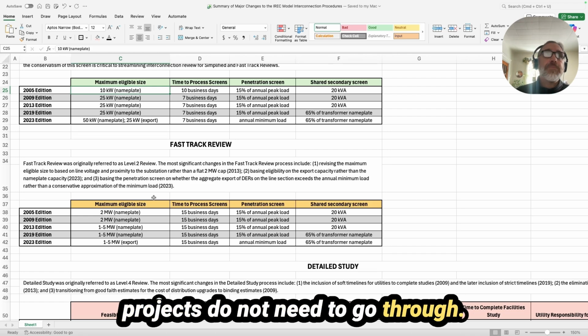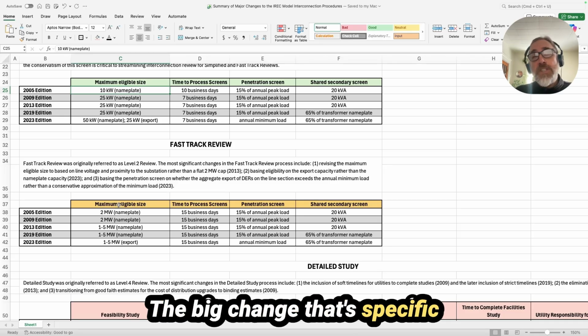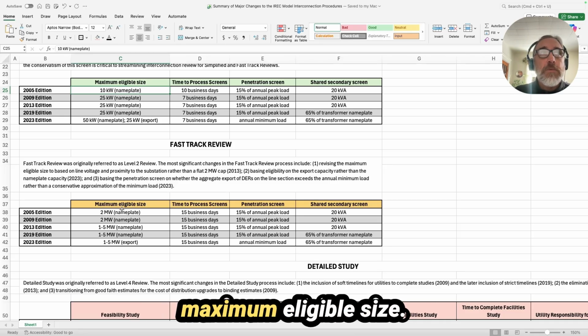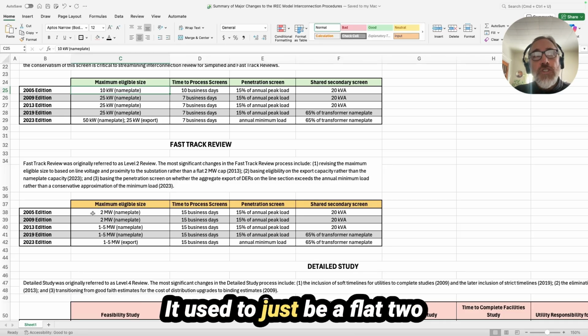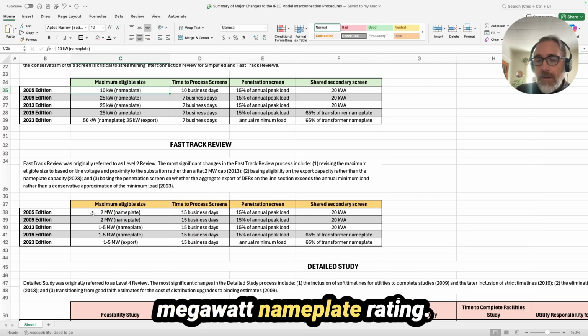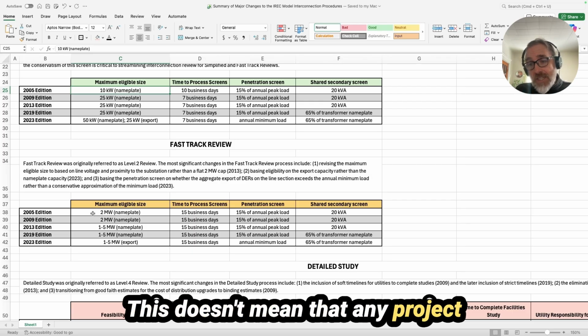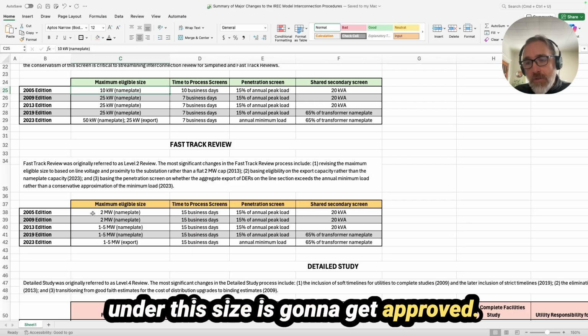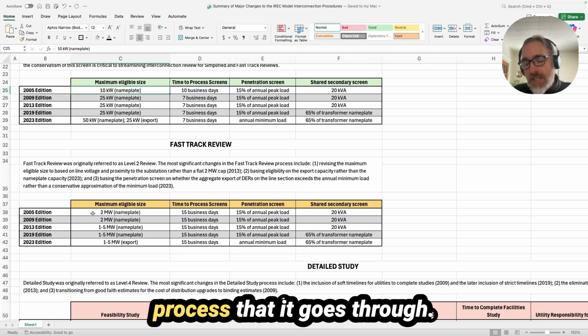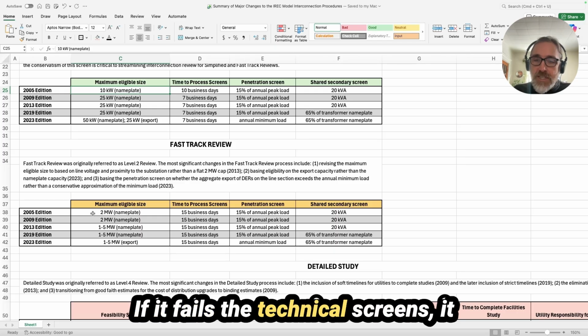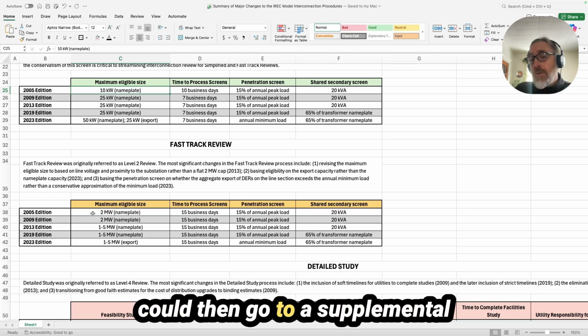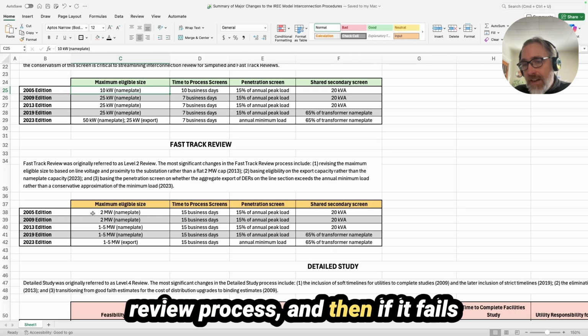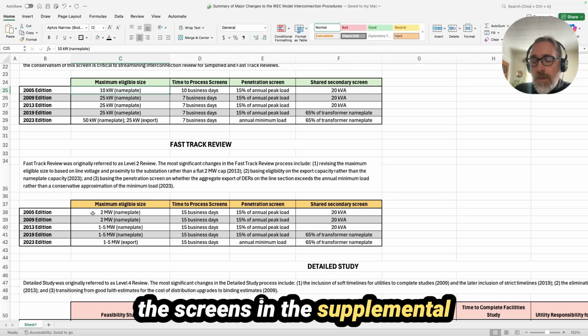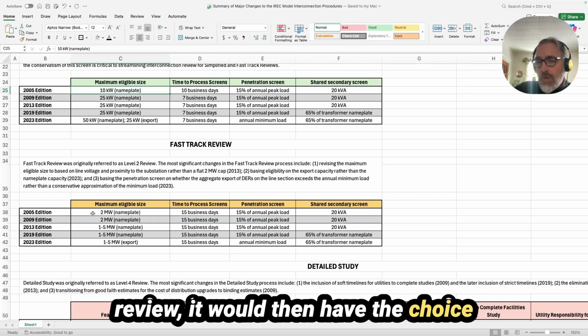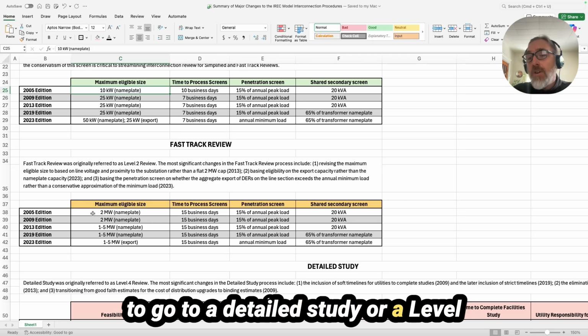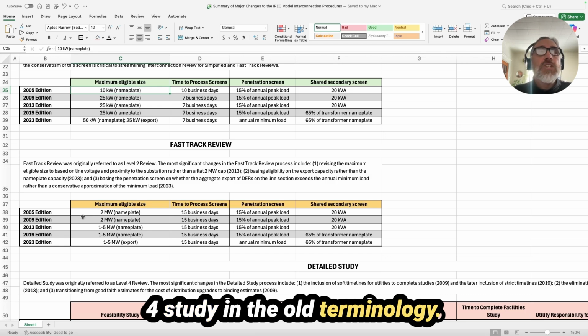The big change that's specific to fast track review is this maximum eligible size. It used to just be a flat 2 megawatt nameplate rating. This doesn't mean that any project under this size is going to get approved. It just means that this is the first process that it goes through. If it fails the technical screens, it could then go to a supplemental review process. And then if it fails the screens in the supplemental review, it would then have the choice to go to a detailed study, or a level 4 study in the old terminology.